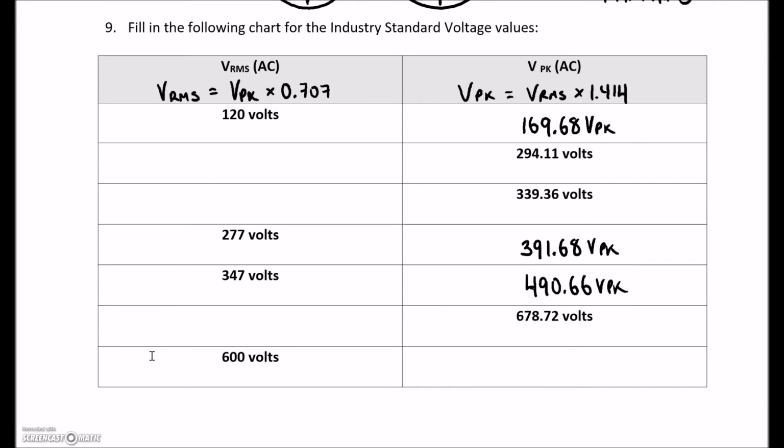Not essentially blow them off, but it's going to cook your fingers to the point where they're going to have to be amputated. It's not 347 volts that's causing the cellular damage. It's 491 volts peak. Doesn't matter if this is just there for a couple of milliseconds. That is going to boil your blood and absolutely destroy the cellular structure of whatever that current is going through.